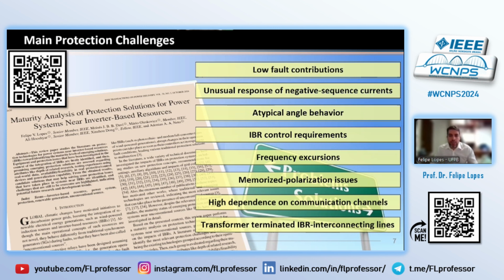Frequency excursions, which are problems much more related to grid following IBRs. As I mentioned, the PLL may present instabilities resulting in frequency excursions. Memorized polarization issues, for instance, because when these frequency excursions take place, the pre-fault data which was memorized quickly becomes invalid. So there are a lot of papers reporting problems related to this type of solution. And we have also read some works reporting the high dependence on communication channels, and also the problem of transformer terminated lines, which is the topology of most existing IBR interconnecting systems.